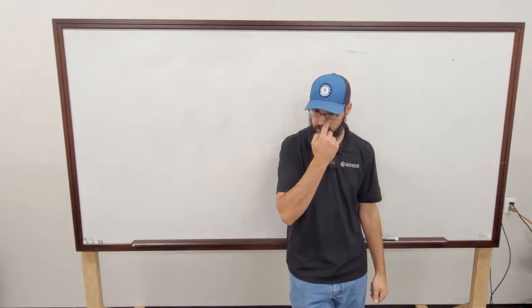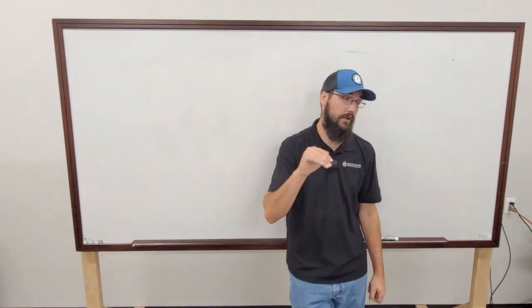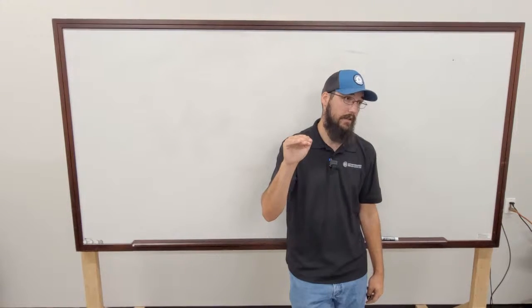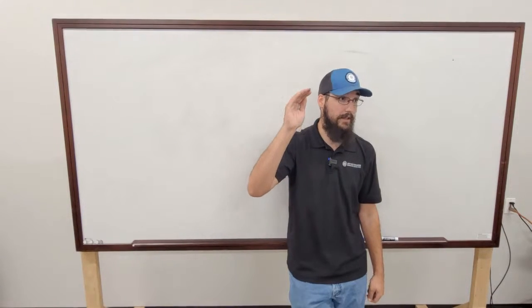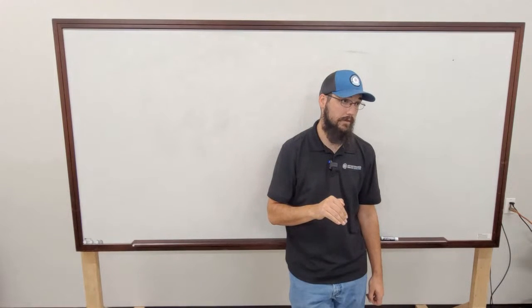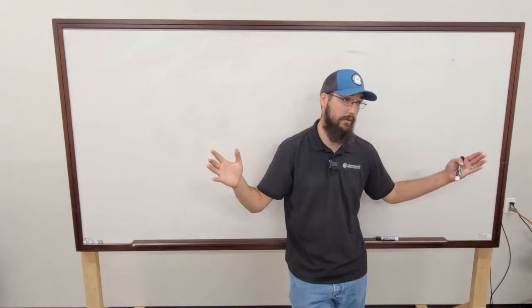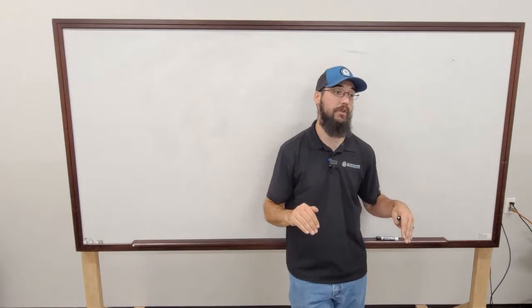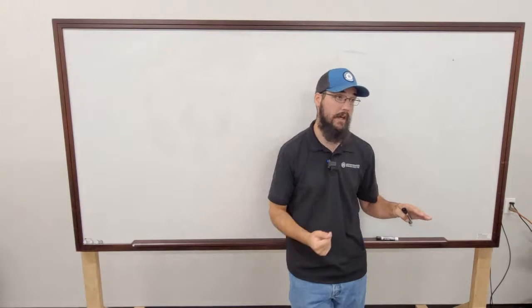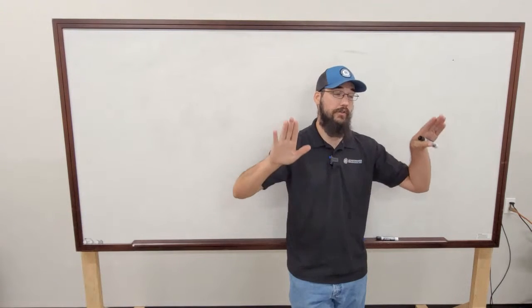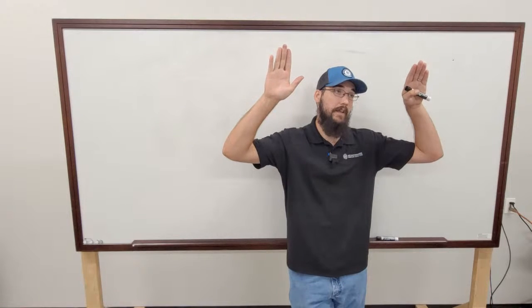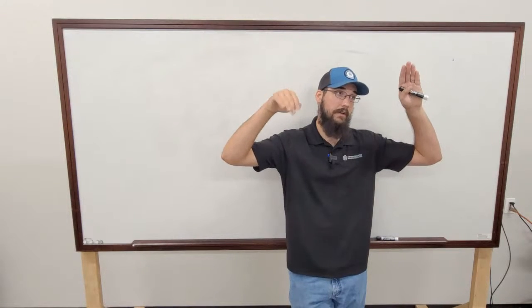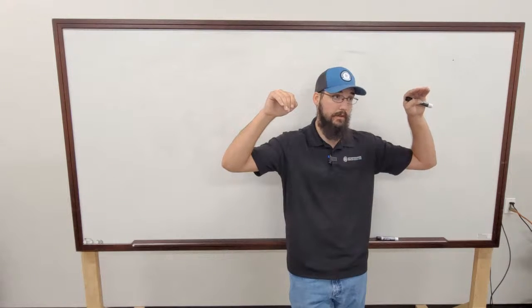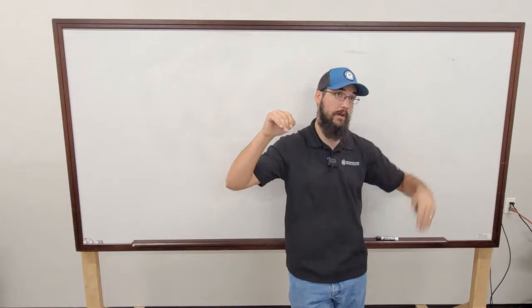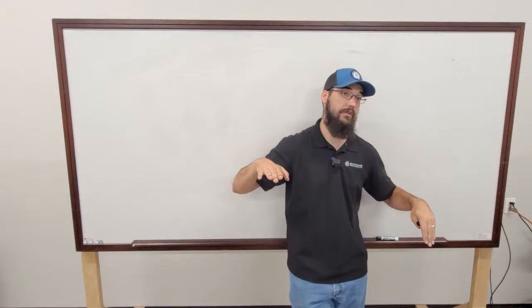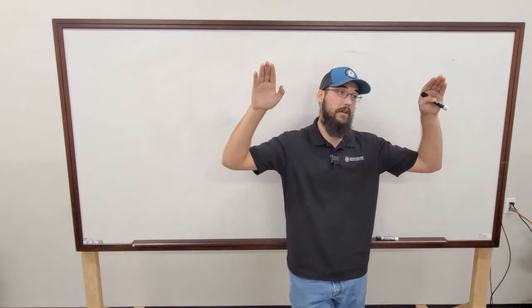York, on the other hand, does exactly that. If it goes to bring in a second circuit, especially because of the VSD, it ramps whatever circuits are running, even if you've got a 3-circuit machine, down to minimum, brings that extra circuit in, and then all the circuits will ramp back up together. And as I'm sitting here talking about it, I think I'm saying that wrong about Trane on the screws specifically. I think on Trane screws, it will ramp those down, bring in the other circuit, and then allow both circuits to ramp up together based off of current limit.